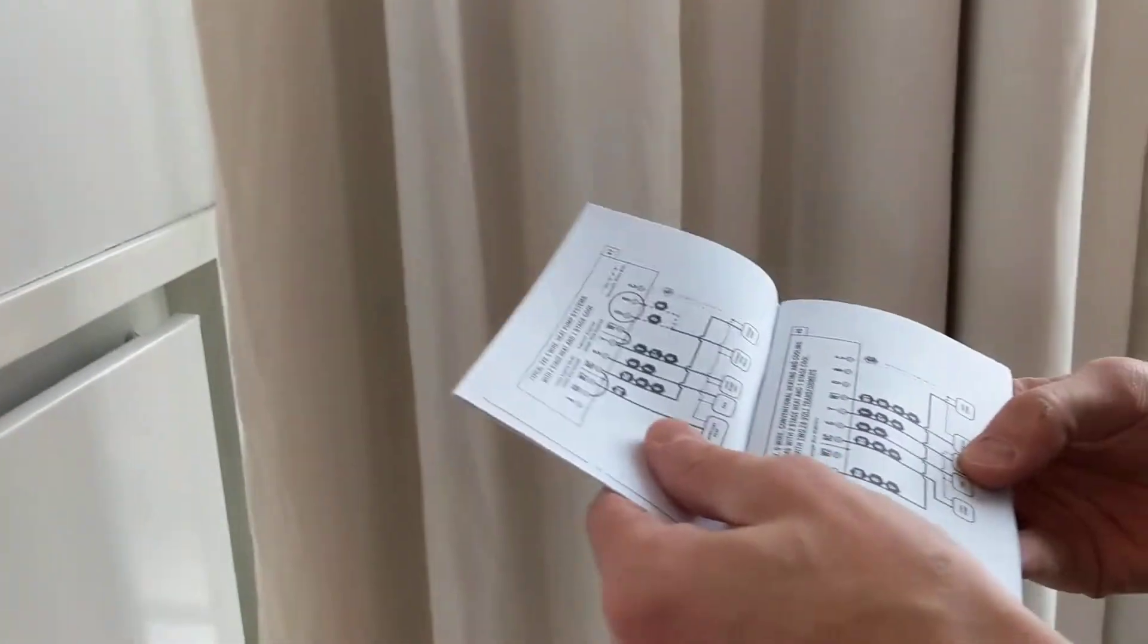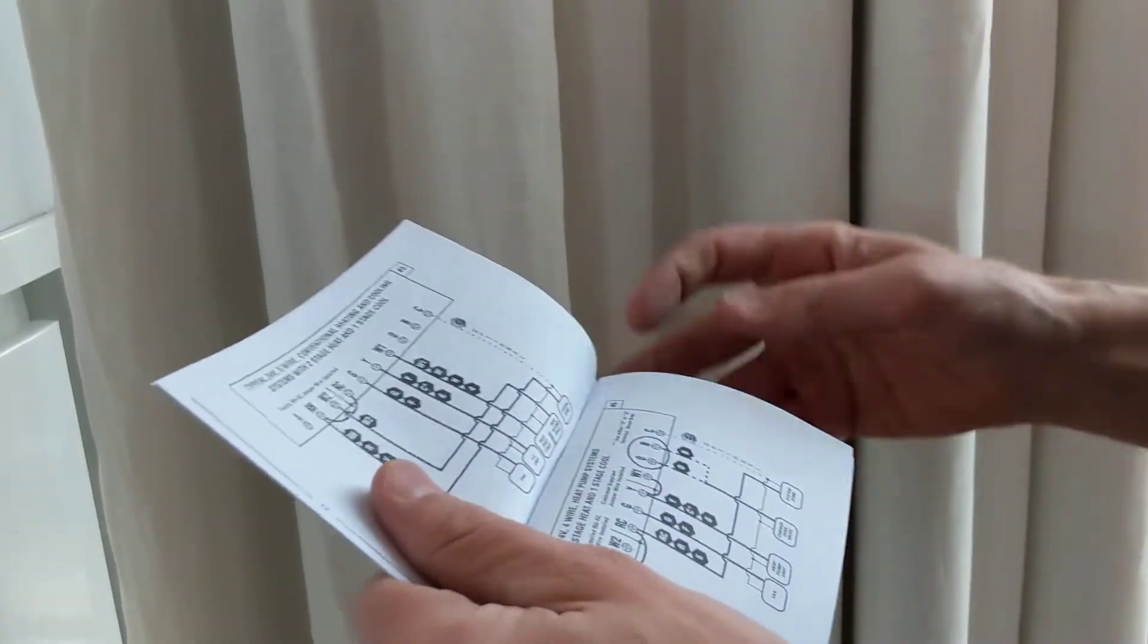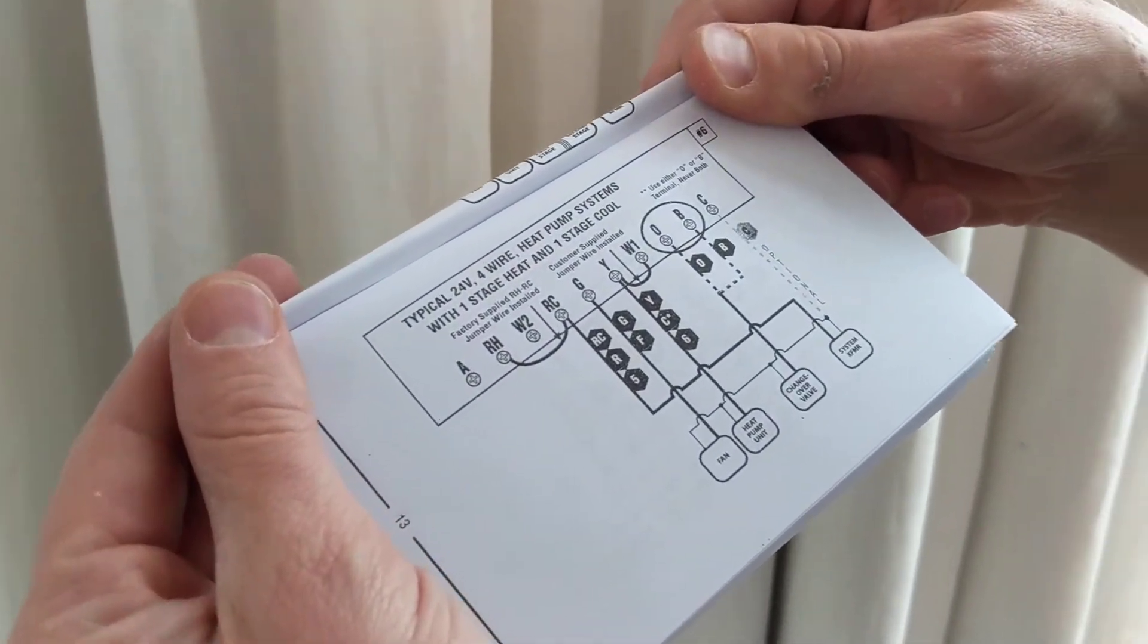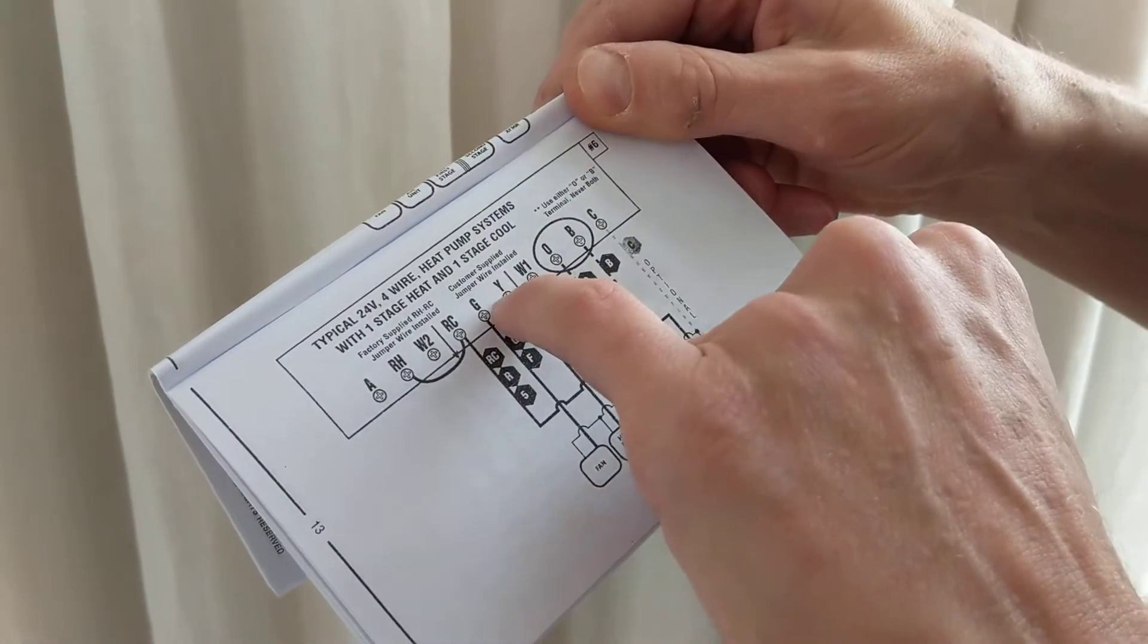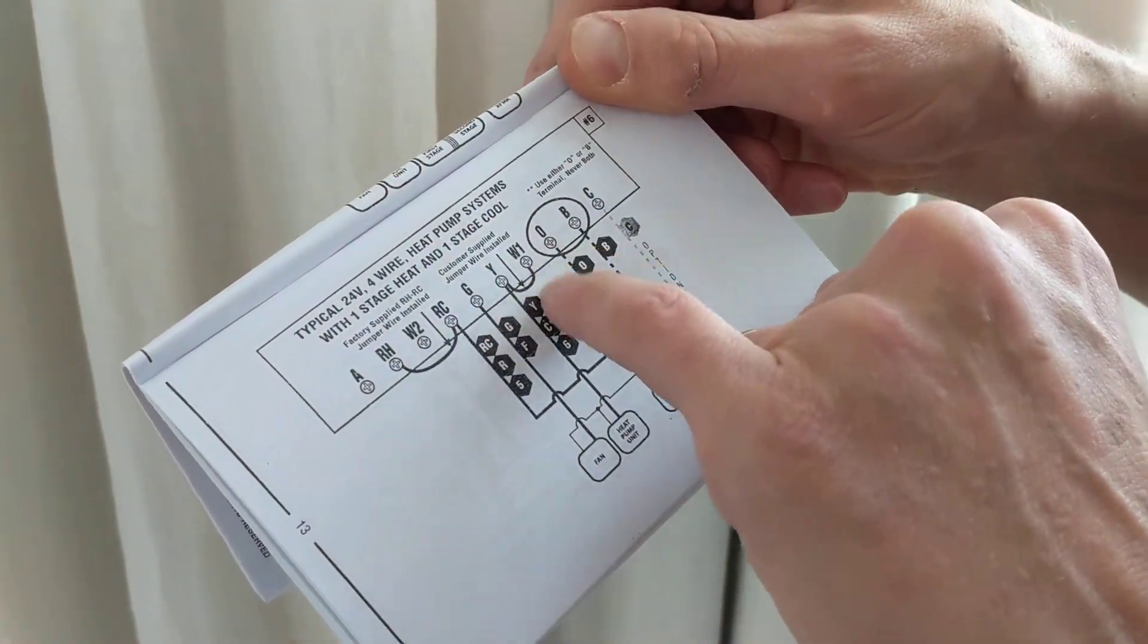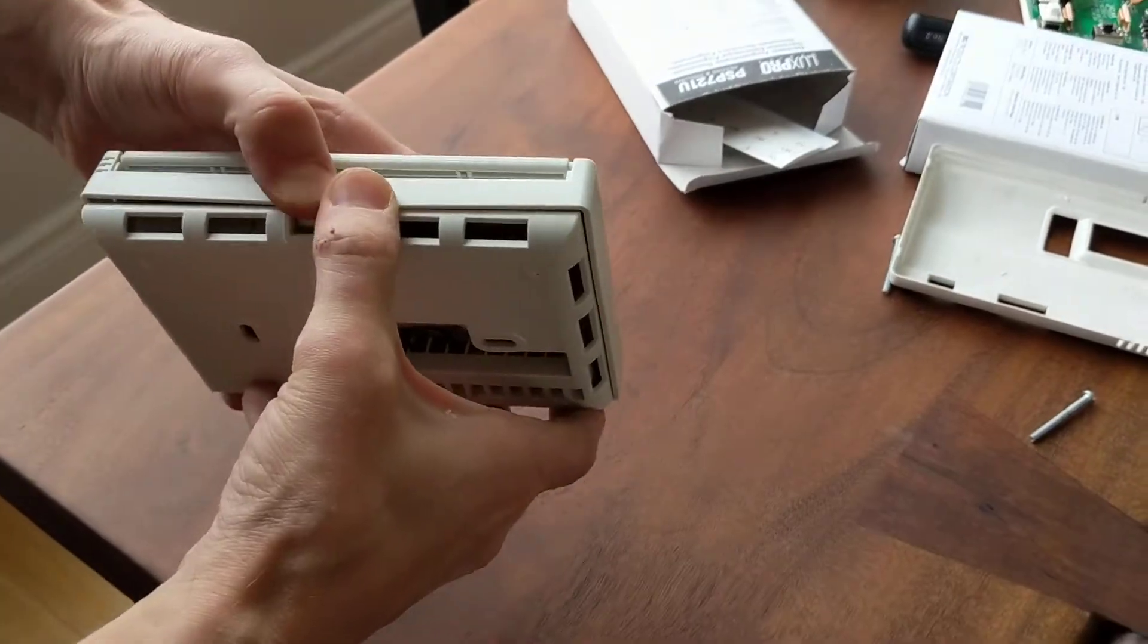Inside there is a manual and we want guide number six. It's a four wire heat pump system. One stage heat, one stage cool. And here's where it shows Y going to W1. And then we're going to attach that one. This other one already comes built in. So we've taken it out of the box. Open it up. Same sort of thing.